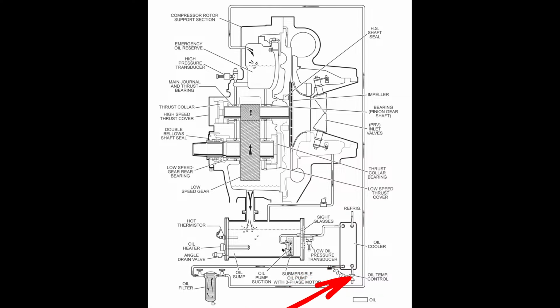But as you see your load increases, this metering valve may not be keeping up. It may be stuck or just not working correctly. And keep in mind, we're not monitoring suction superheat coming off of this, because this is just feeding back into the evaporator on these machines, which is not like a regular refrigerant circuit. We were worried about flooding. That's not a concern here. Even if we do have liquid refrigerant leaving this heat exchanger, it's just going back into the evaporator, which has standing liquid in it. It's not a concern.